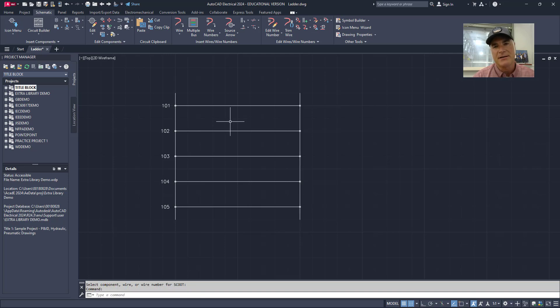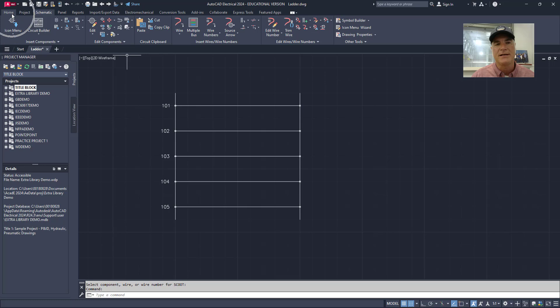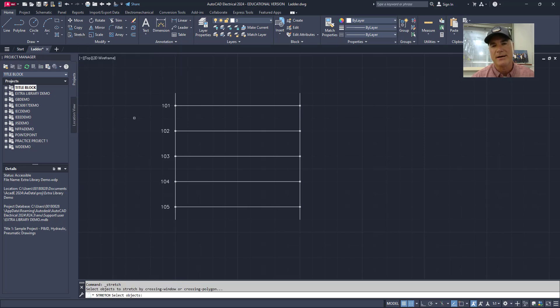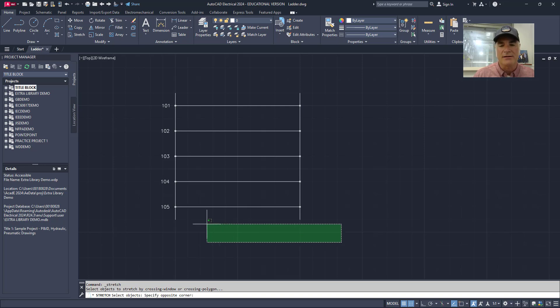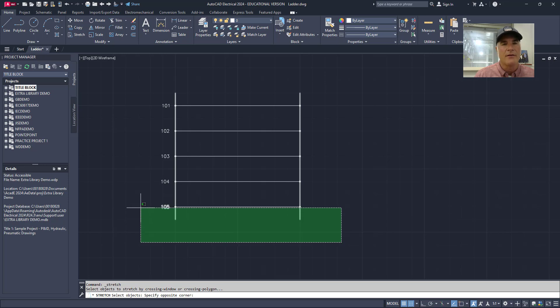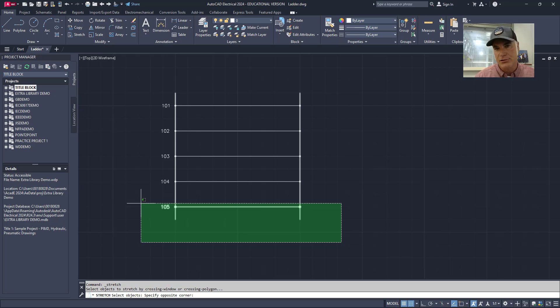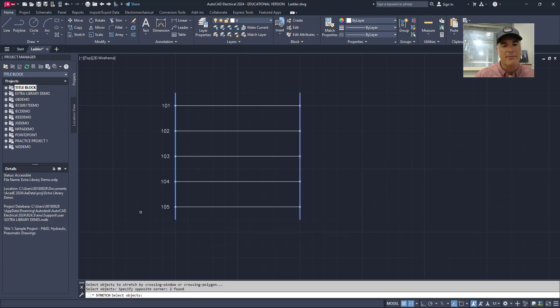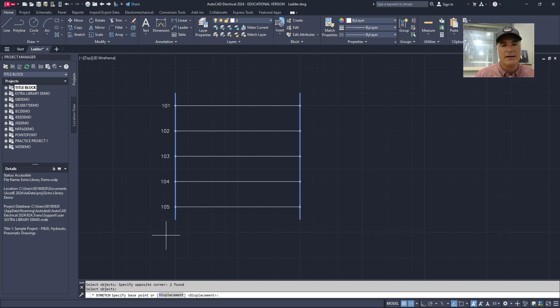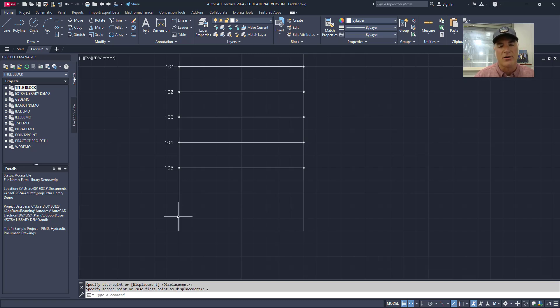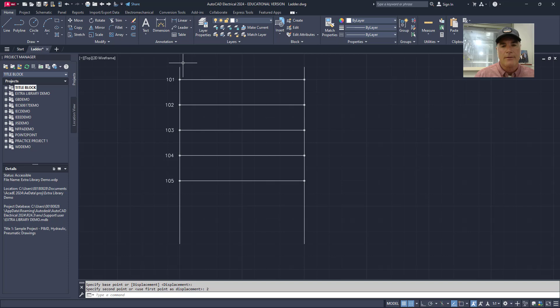If I need to make the ladder longer, there's a couple steps that are involved. The first step is to go to the home tab up here on the ribbon and use the stretch command. When you use the stretch command, you have to stretch by selecting your objects with either a crossing window or a crossing polygon. I'm going to use a crossing window and I'm only going to select the bottom of each of those rails. I don't want to select the number on the left hand side or a rung because that's going to stretch that rung as well and I want it to stay where it is. So it's important that you only select the bottom of those two rails. Once you're done selecting, you can press enter and then you can select your base point and then your second point of where you want it to be stretched out to. In this case, I'm just going to pull it down. I'll type two to make it two inches longer.